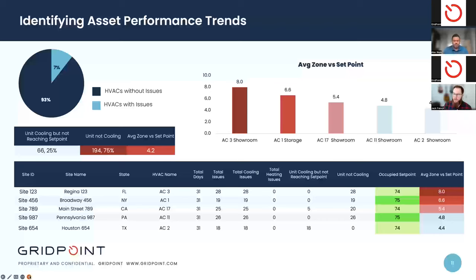This can give you an informed decision on, hey, do I just need to make a set point change here? Am I being a little too aggressive with my set point? All of these are between 74 and 75, so these are very conservative in terms of the energy consuming direction. But say you have a unit that's set to 68 degrees and you're constantly trending at 72. Well, why not set that set point to 72? Because the unit can meet that set point consistently, but it can't meet 68. So that's going to reduce wear and tear on your unit and extend unit lifetime.